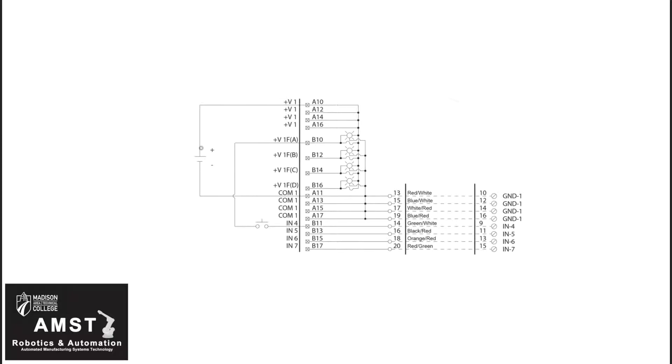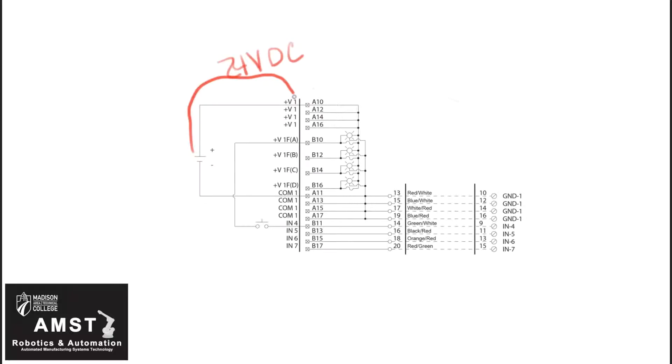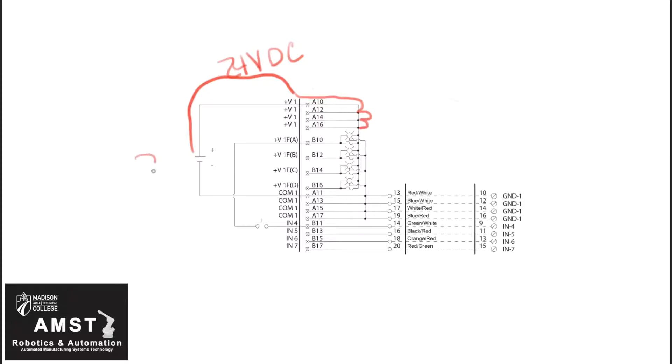Now we just have 16 of our 64 terminal screws to figure out. Let's look at our 24 volt and how it connects to terminal A10. That brings 24 volt supply into the IFM. That, in turn, is jumpered to A10, 12, 14, and 16. So all four of those terminal screws are connected to each other internally. Connecting one wire to A10 takes care of 12, 14, and 16 as well.